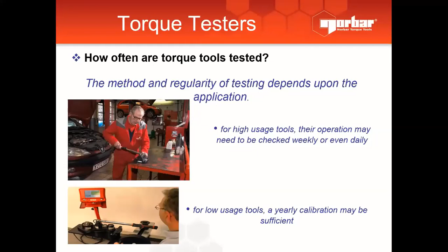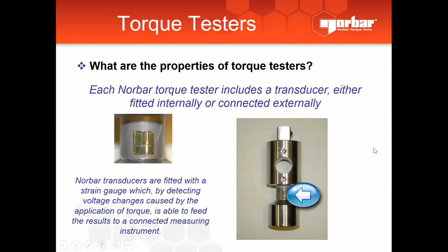What are the properties of this torque tester that let it collect results? The torque tester design is based on a shaft. We have a smart chip that connects to wires, which gets the twist and strength and sends it to the tester itself. This is where our transducer is. Then it feeds back to the display and converts into the torque value.